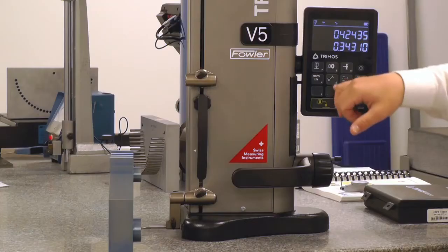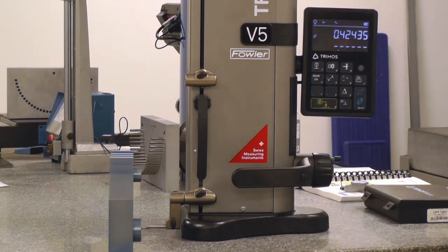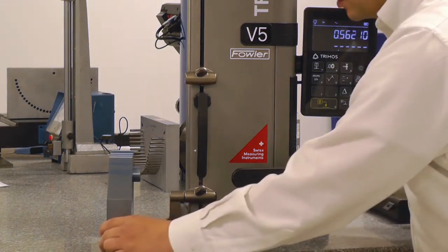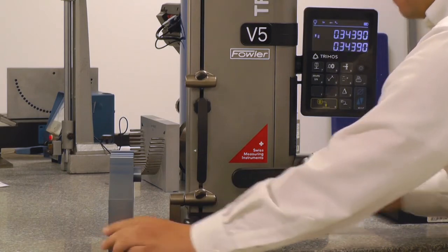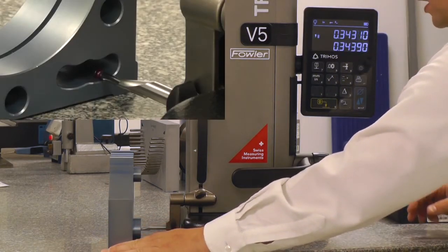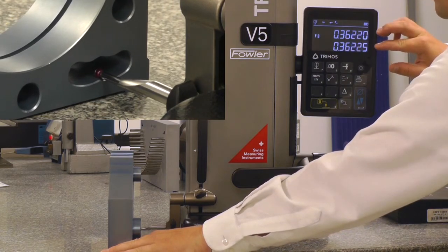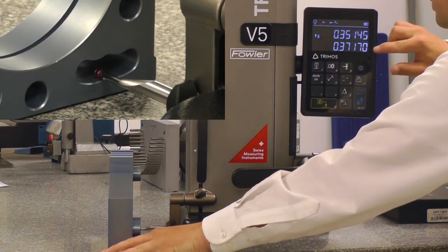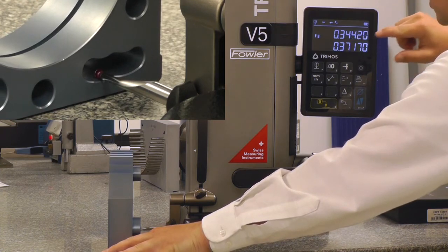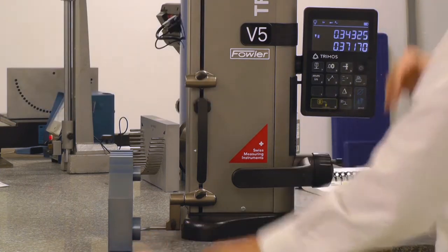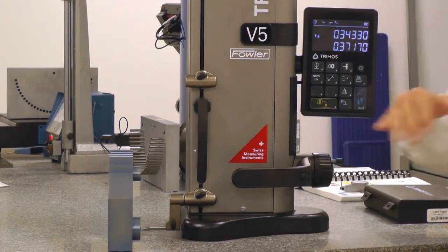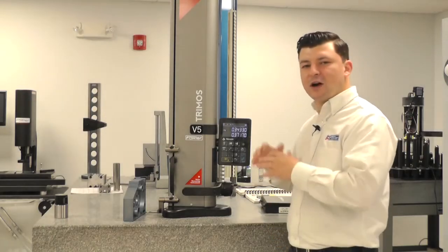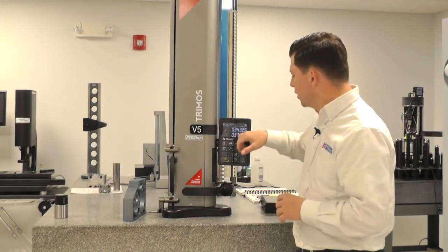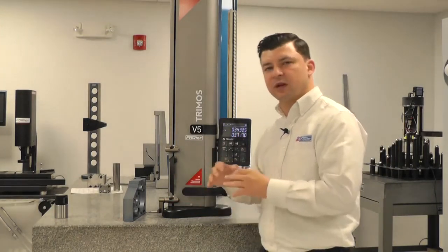In the same sense, if I wanted to know the max, if I hit this number 5 button again, that's going to toggle me to my maximum function. That's going to lock on the highest point. So if we sweep across the high point, I'll engage my probe, and again my numbers will travel up. As they're growing, we're going to find that peak. Once we cross that peak, my number locks on, and my numbers on the top line start to drop back down. So that top line is giving me the current position wherever the probe travels, and this bottom number is locking on the max. So 371 thousandths is my wall thickness relative to the top of that peak.